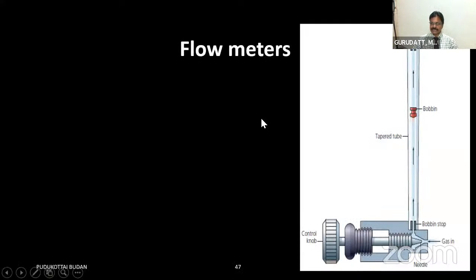Coming to the flow meters, the flow meter assembly. You can see the flow meter here. These flow meters are tapered, and as you go up, the area of the flow meter increases. That means the space between the bobbin and the inner wall of the flow meter keeps on changing, a varying annular space. That's why it is also called a variable orifice flow meter.